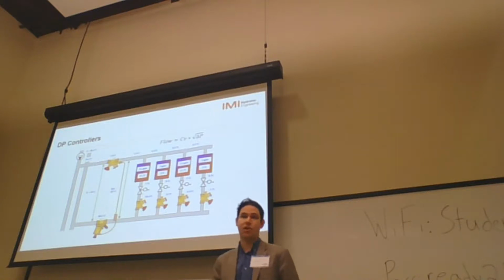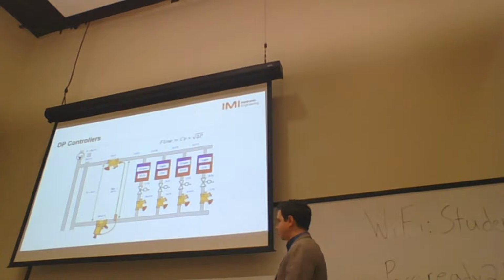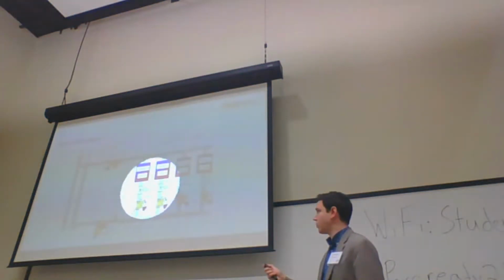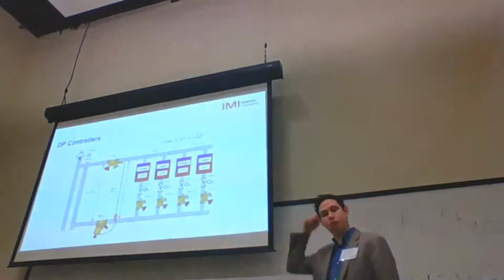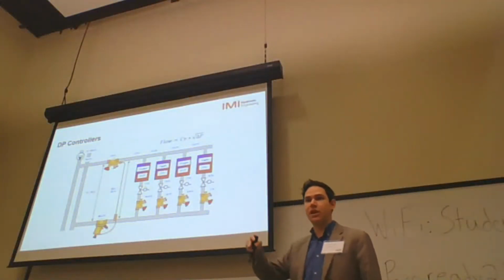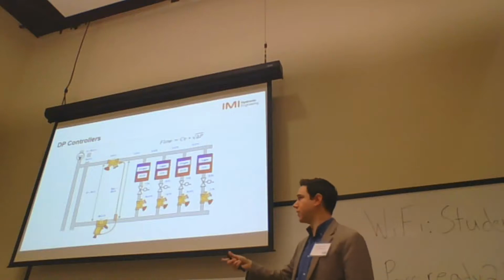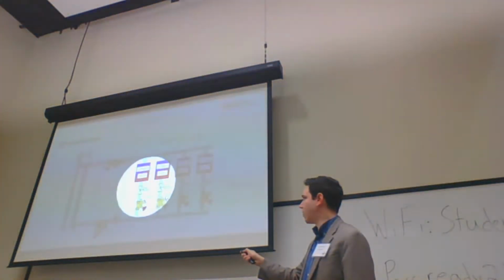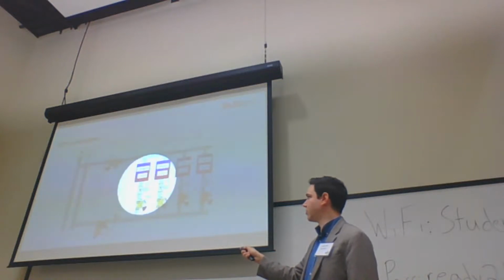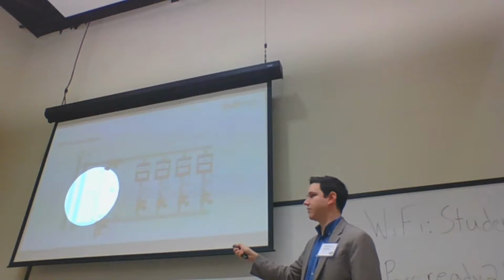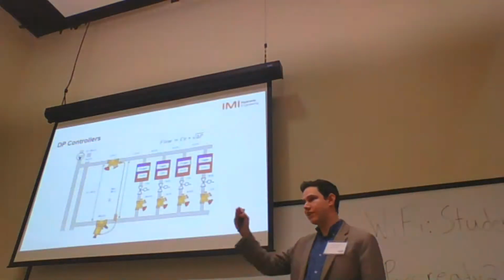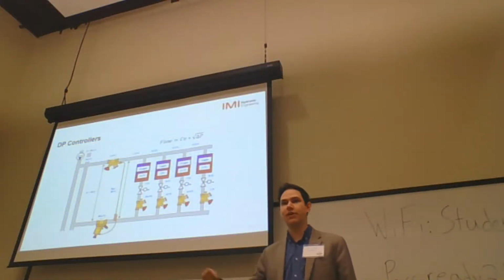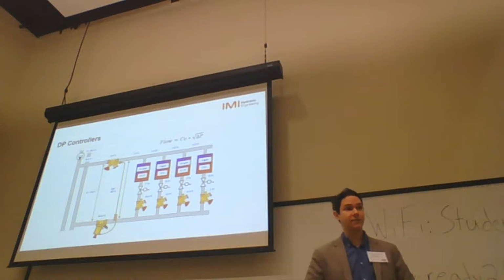And by doing that, you get a lot of benefits. First, you improve the control valve authority. So if you look at this control valve right there, 7 feet pressure drop. If you remember the previous slides, the calculation of authority is the pressure drop of the control valve divided by the available pressure. So without the DP controller, it would be 7 divided by 70 feet. With the DP controller, it's 7 divided by 28. So 7 divided by 28 is a much better number than 7 divided by 70.